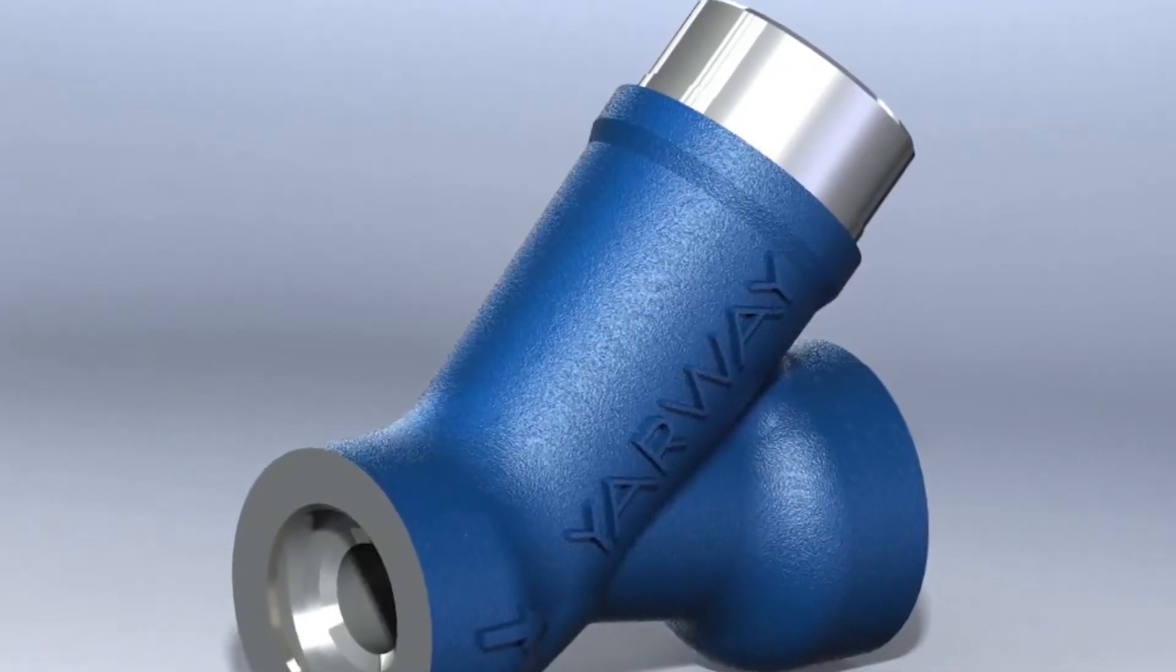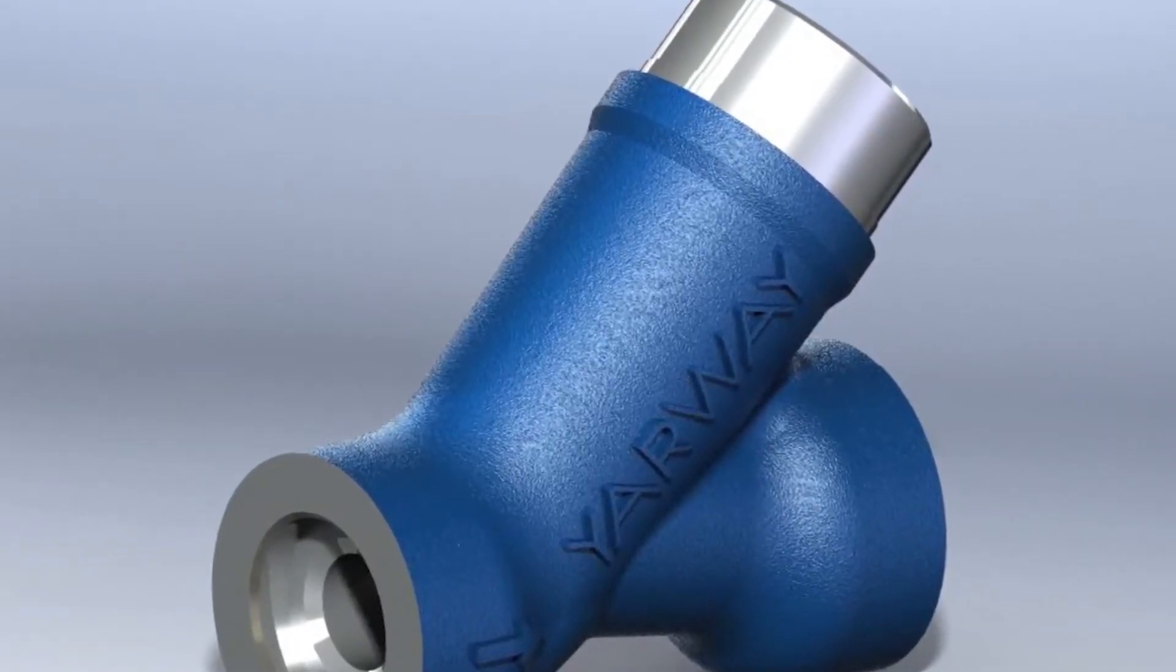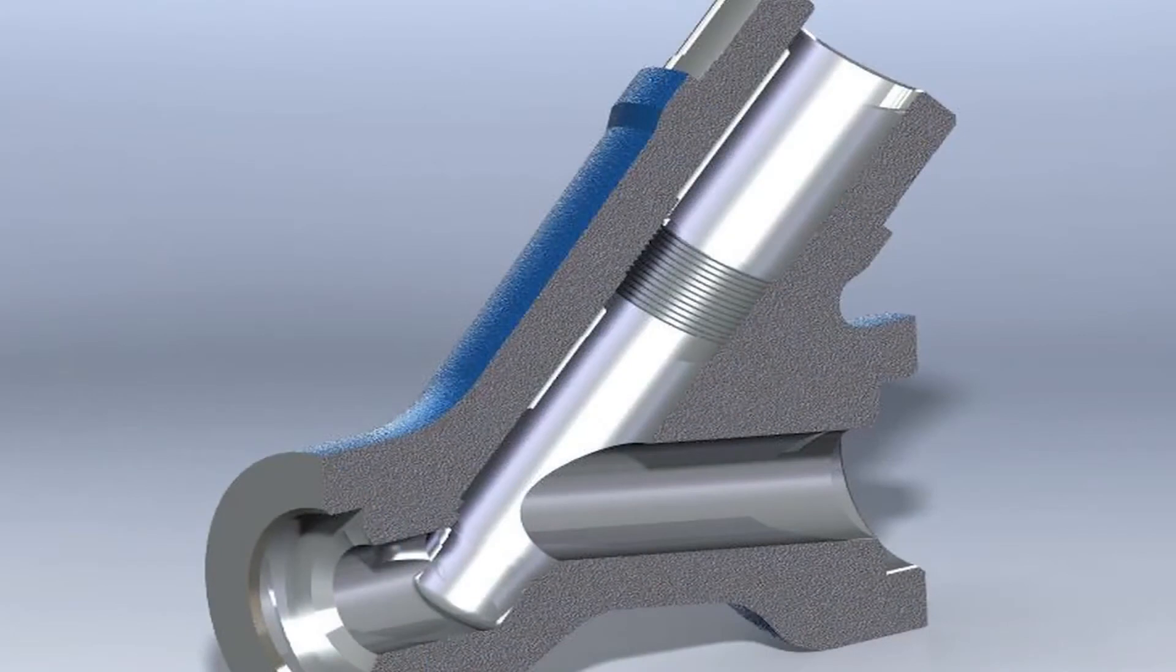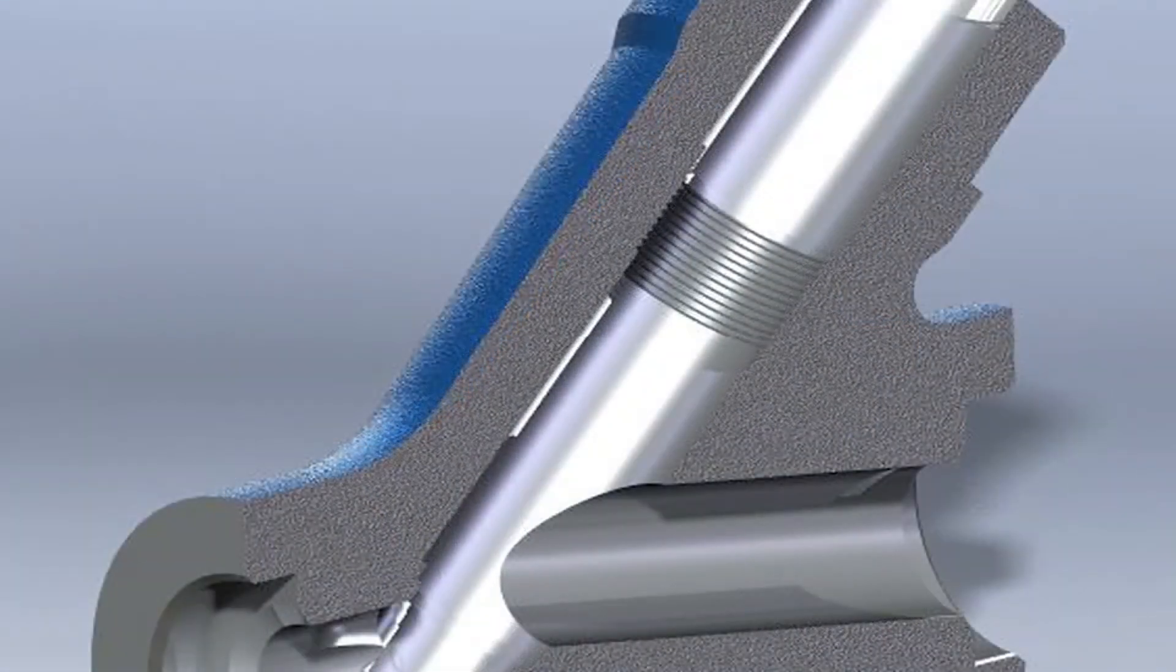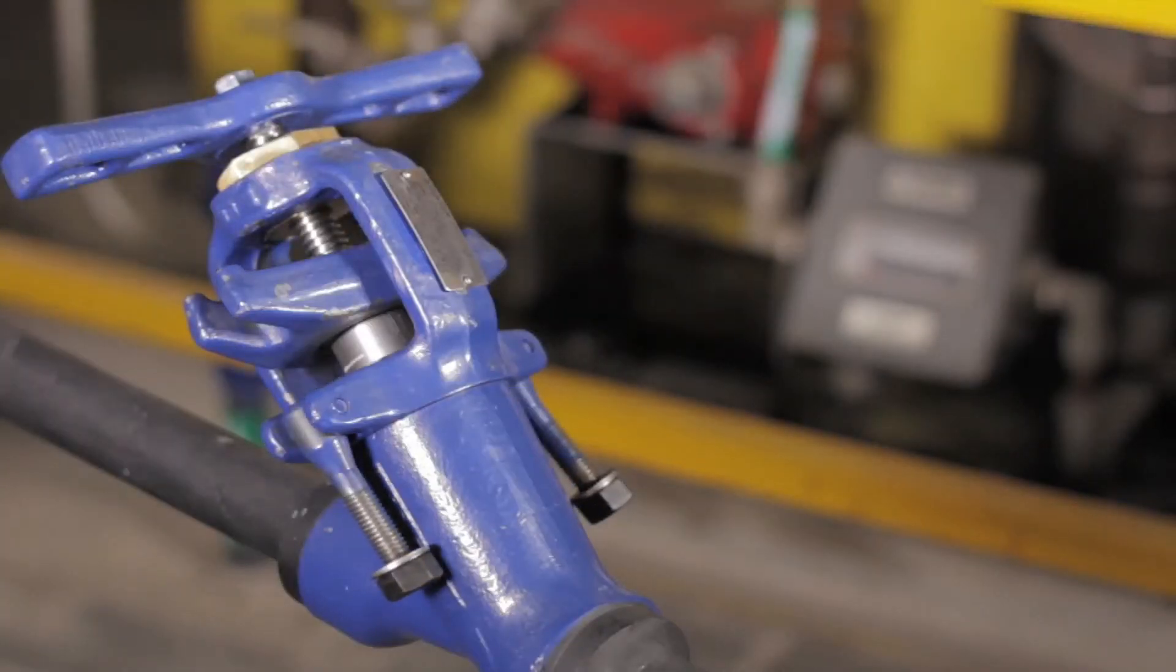Now let's go through the steps for reconditioning a Welbond valve with the fixed backseat design. For demonstration purposes, we have turned this valve into a fixed backseat model. Such a conversion is easy because both valves use the same body with internal backseat threads.